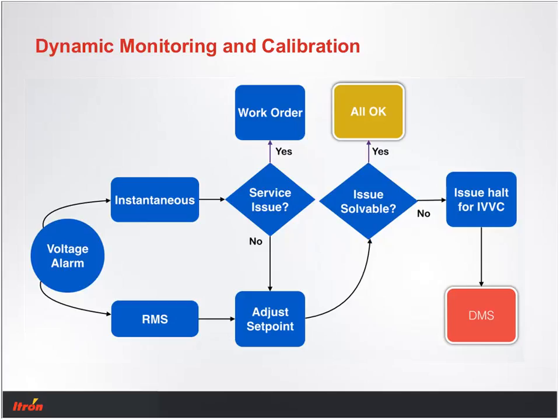You can think of these two pathways, the instantaneous and the RMS: the instantaneous would be a violation of tariffs, so we've gone below 114 or above 126. You can think of the RMS as more of a set point type of value—if we had targeted 116, for example, that indicates we've gone below the 116 level. So what we're trying to understand is our position with respect to our lower set point and our position with respect to tariff.